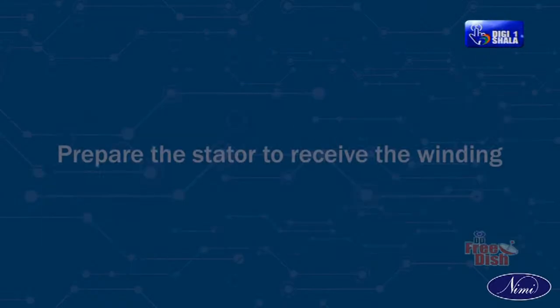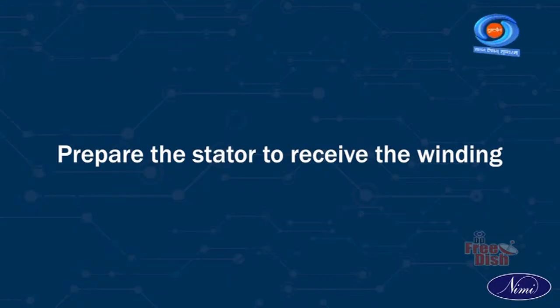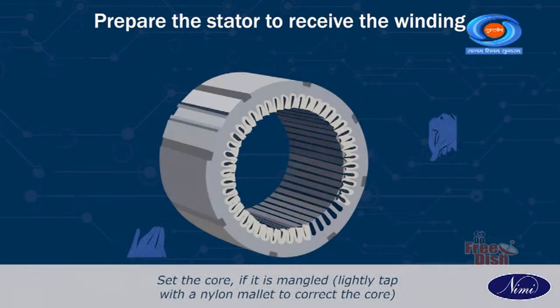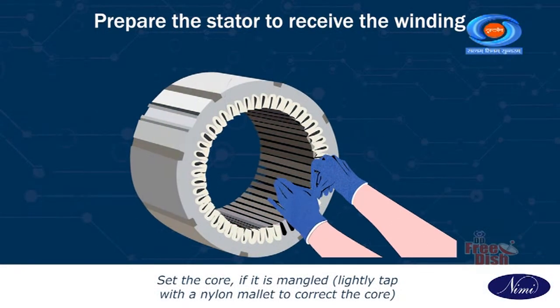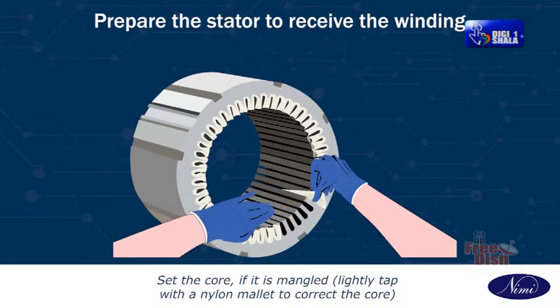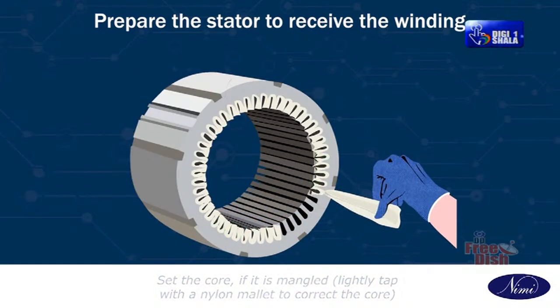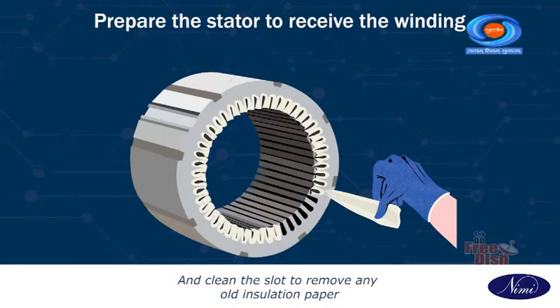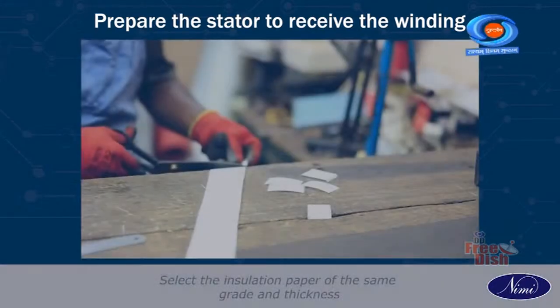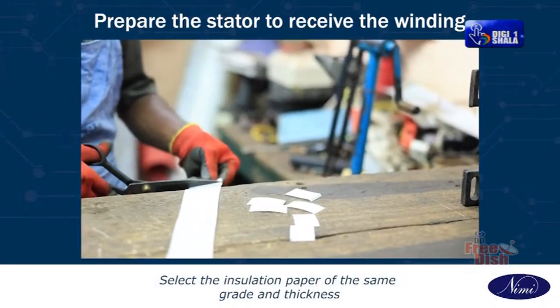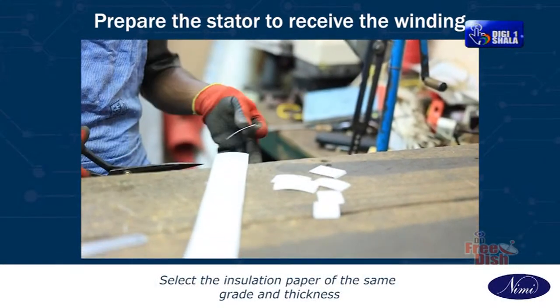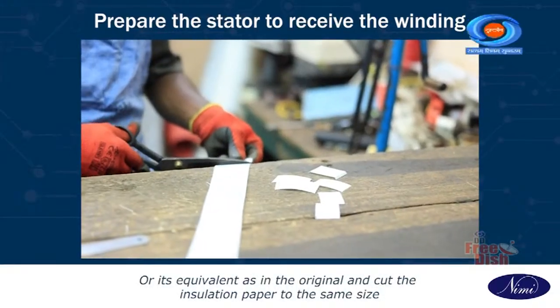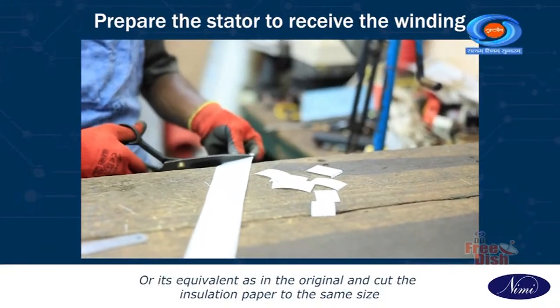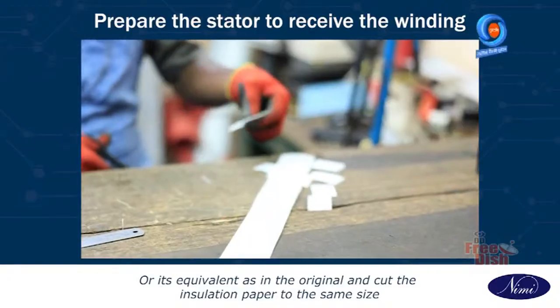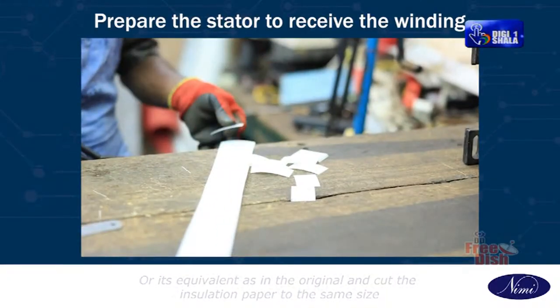Task 2. Prepare the stator to receive the winding. Set the core if it is mangled. Lightly tap with the nylon mallet to correct the core and clean the slot to remove any old insulation paper. Select the insulation paper of the same grade and thickness or its equivalent as in the original and cut the insulation paper to the same size.